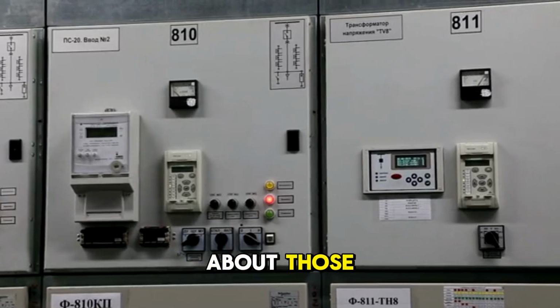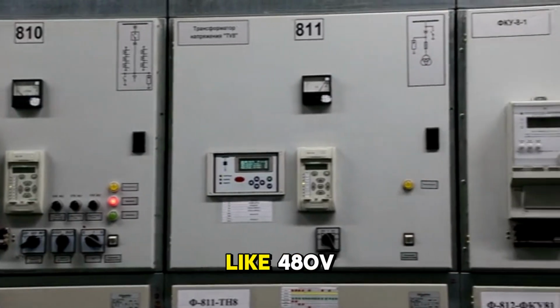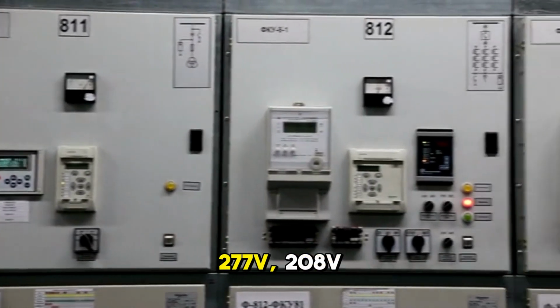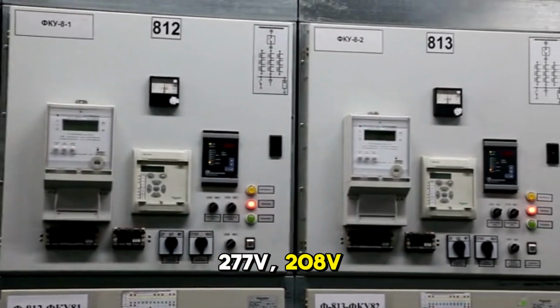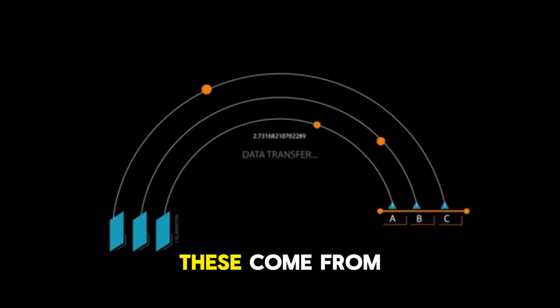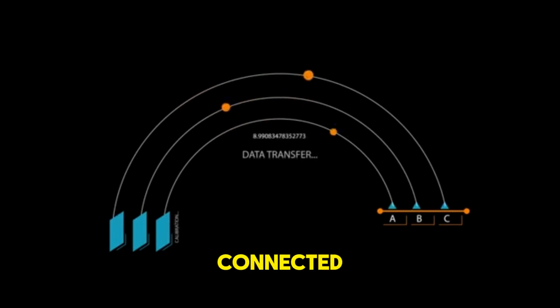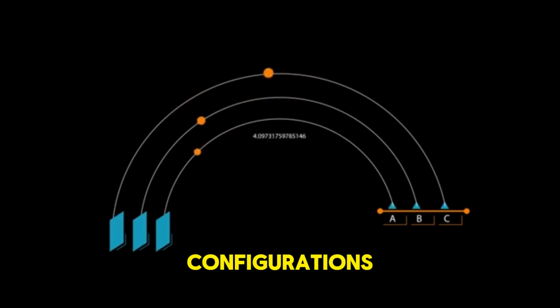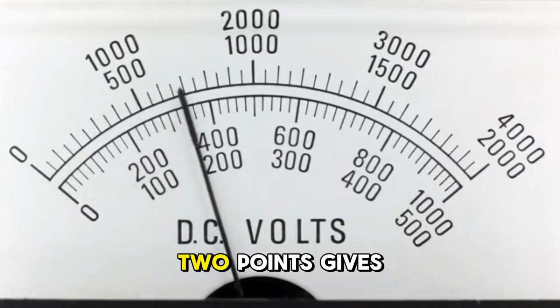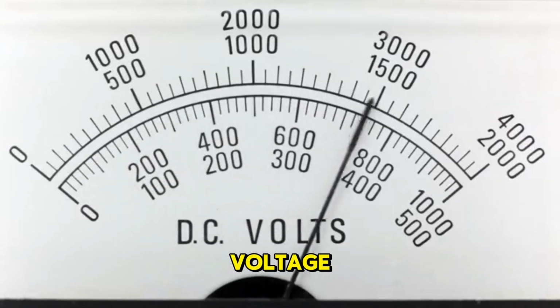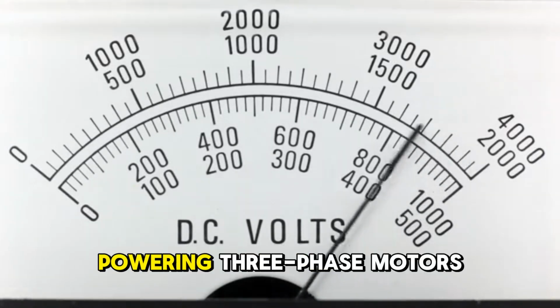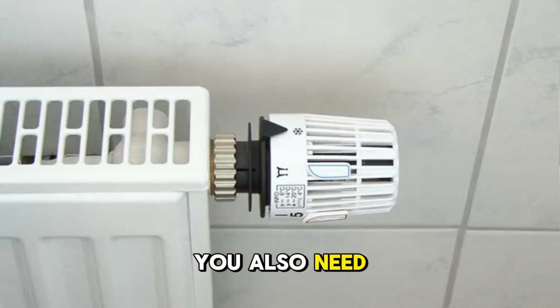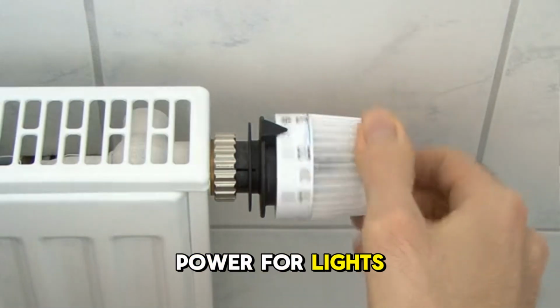Now, let's talk about those different voltages you hear about, like 480 volts, 277 volts, 208 volts, and 120 volts. These come from how the secondary coils are connected, which leads us to Y and delta configurations. Imagine the three secondary coils. In a delta configuration, they're connected, forming a triangle shape, like the Greek letter delta. Measuring between any two points gives you a specific voltage, say 240 volts. This is great for powering three-phase motors, but what if you also need standard 120-volt power for lights and outlets?